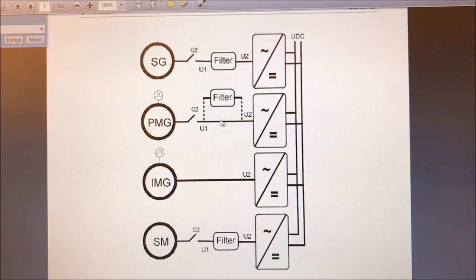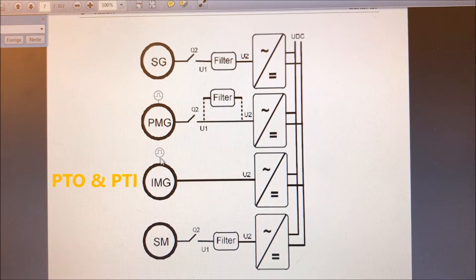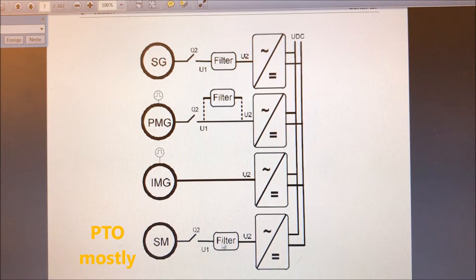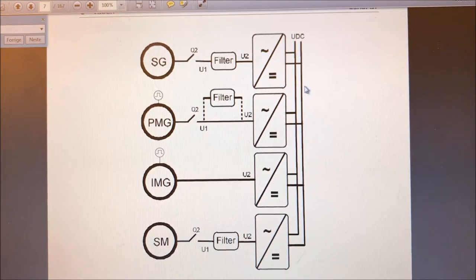This is the same setup as we have in our simulator for the demonstrations. You can also use an induction motor generator, and here you should use a speed encoder for closed loop control. You can also use a synchronous machine with external excitation, and with a filter the functionality will be quite similar to active front end usage — typically in power take-off mode where you produce a DC voltage for its consumers.